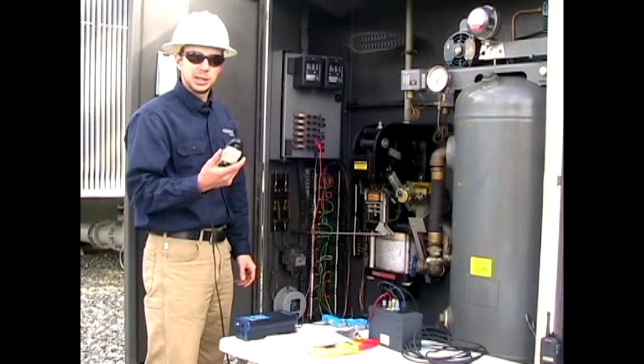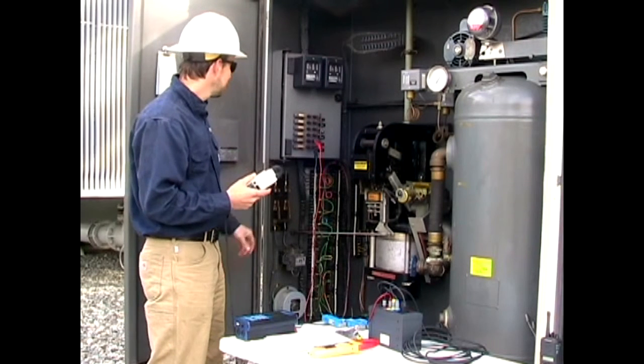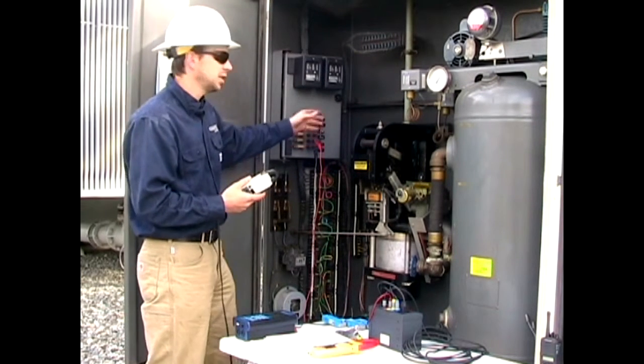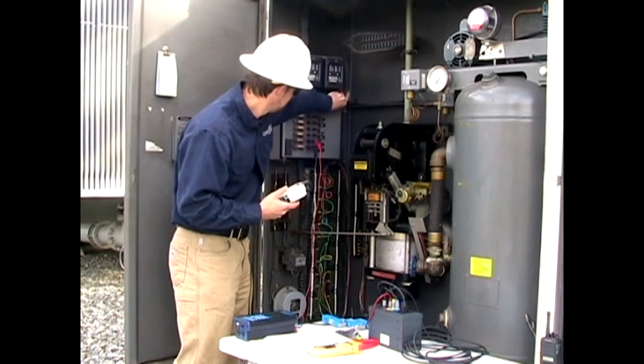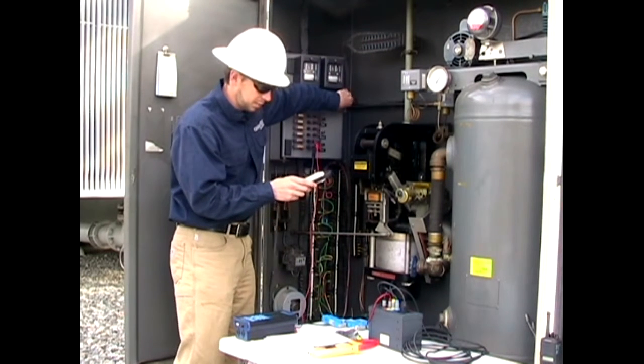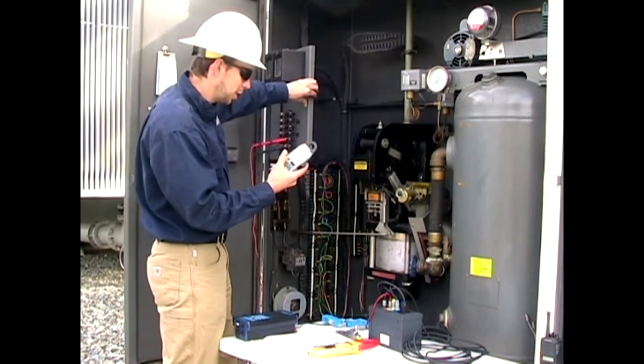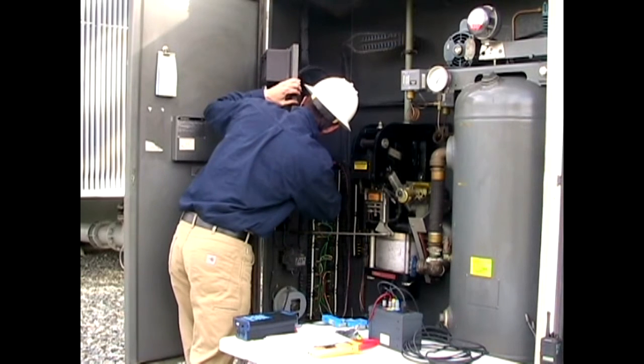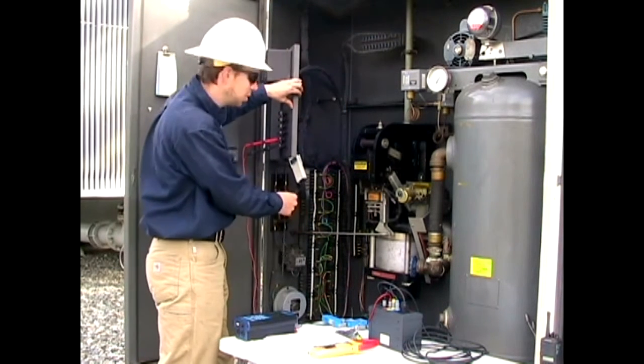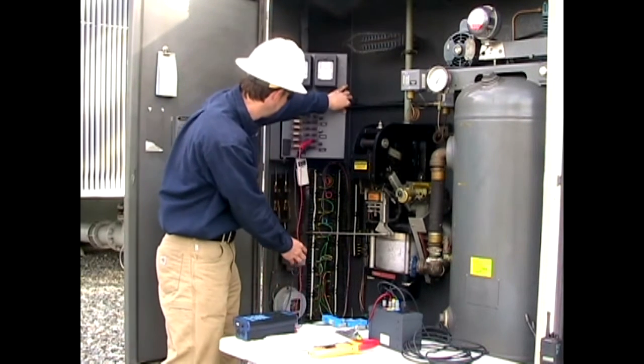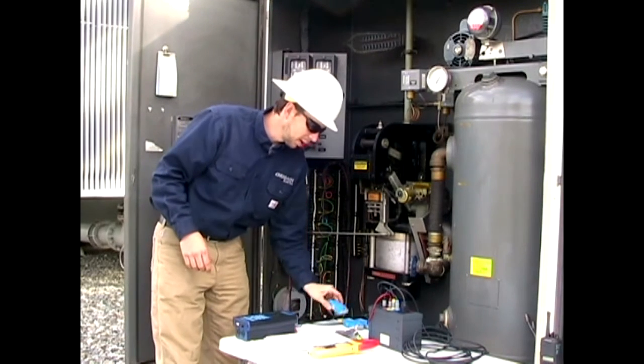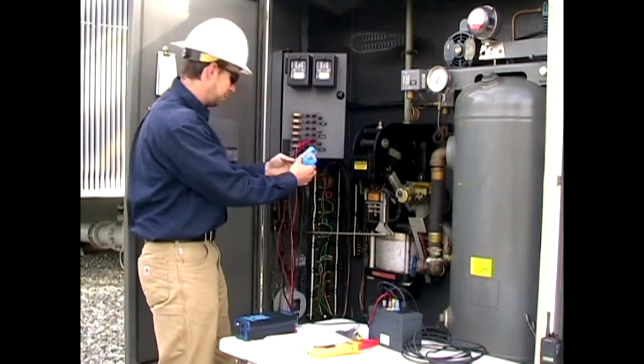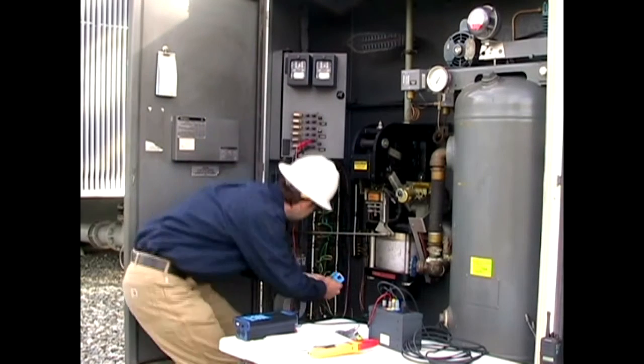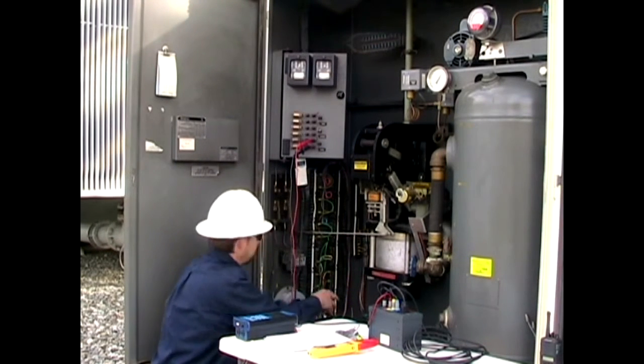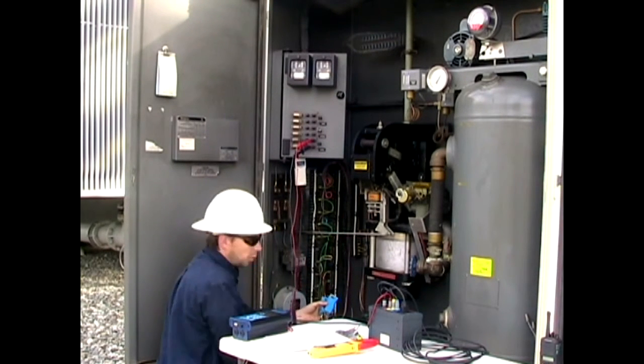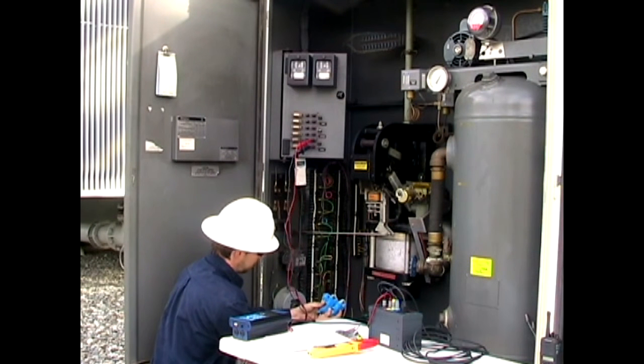So we've already looked at the prints, and the wire that goes to the trip coil is in between this switch and this fuse. The easiest way to get to it is on the back side. So we've turned our current probe on, and we've connected to the wire that leads to our trip coil. So next we're going to put on our CTs. And the prints have verified that 1Y, 3Y, and 5Y are the CTs we're going to monitor.